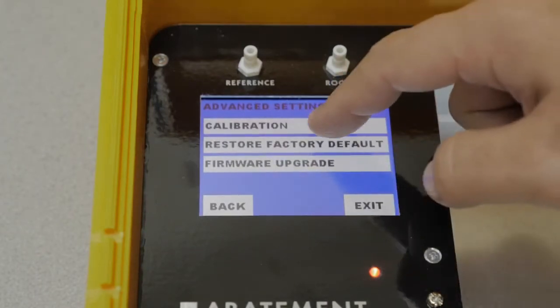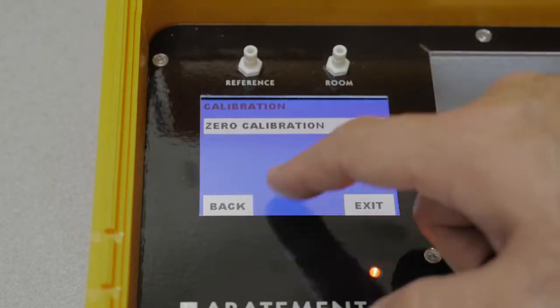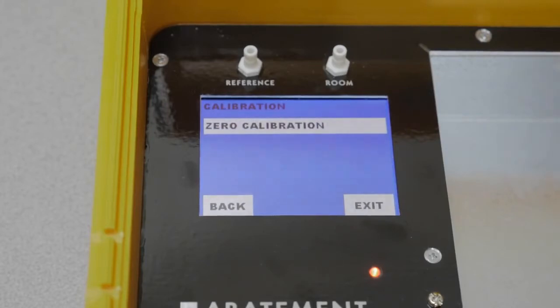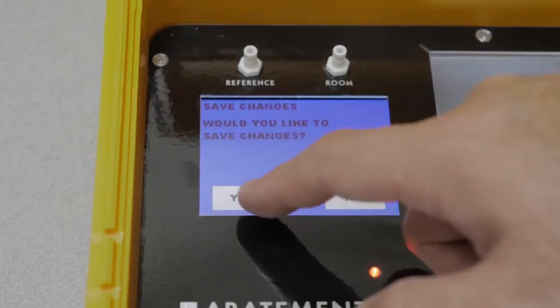Through calibration, you can calibrate after applying zero pressure to all pressure inputs and waiting for the differential pressure to stabilize. The operator will be prompted to press a button to continue.